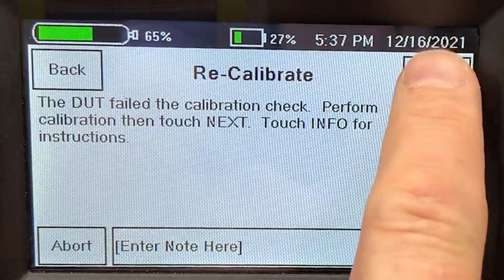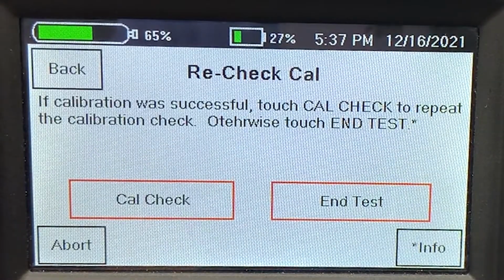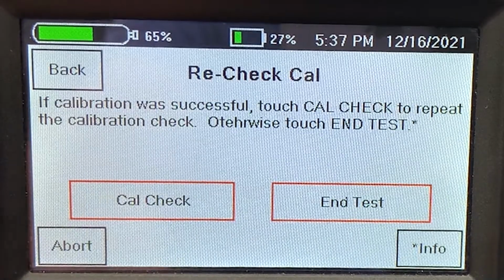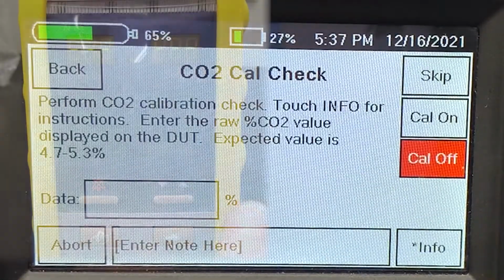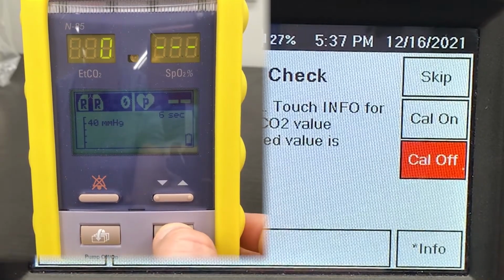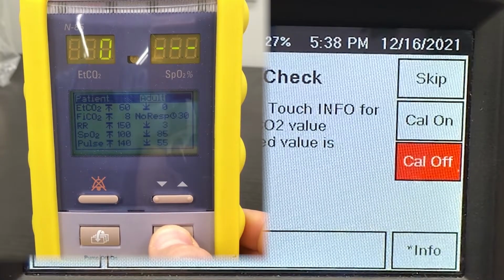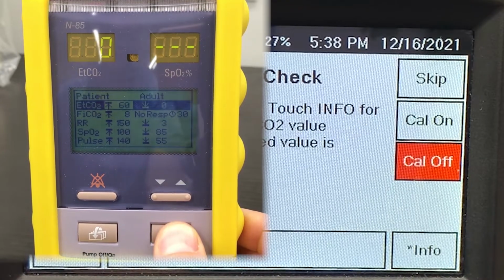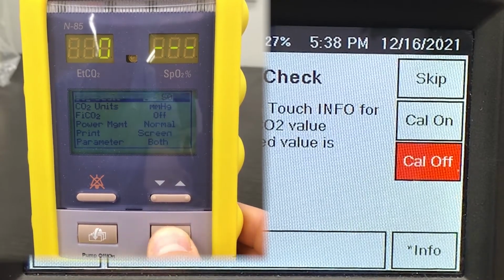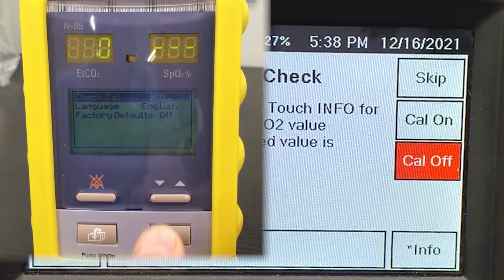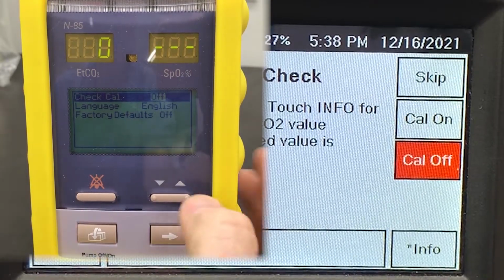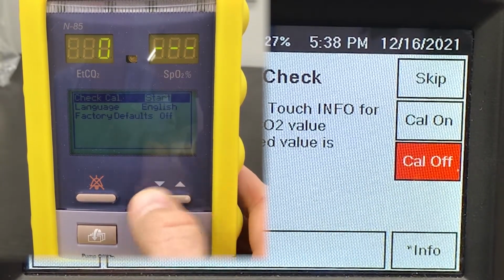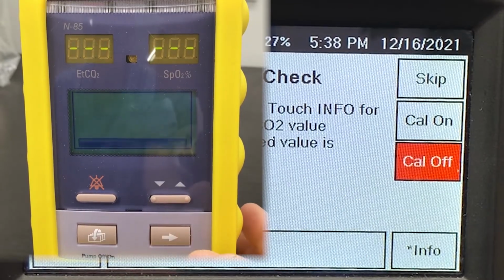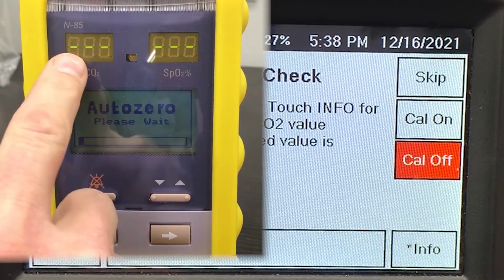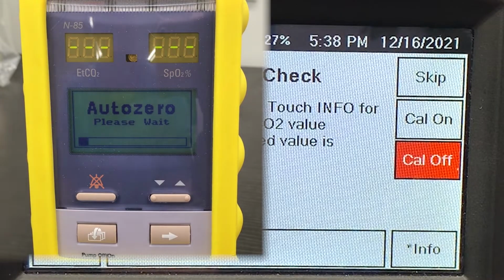So now we're going to touch next on the smart tank, and it will ask us if we want to end the test or run the cal check again. So run the cal check again. Again, we do that by pressing the next arrow, long press again, until we see check cal. Use the up arrow to turn that to start and next. It'll auto zero and then it'll tell us to feed calibration gas.